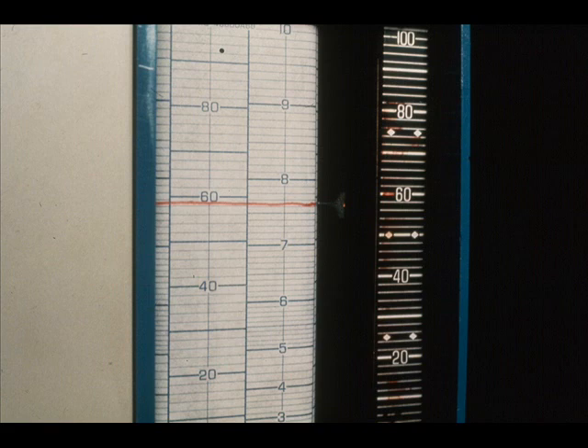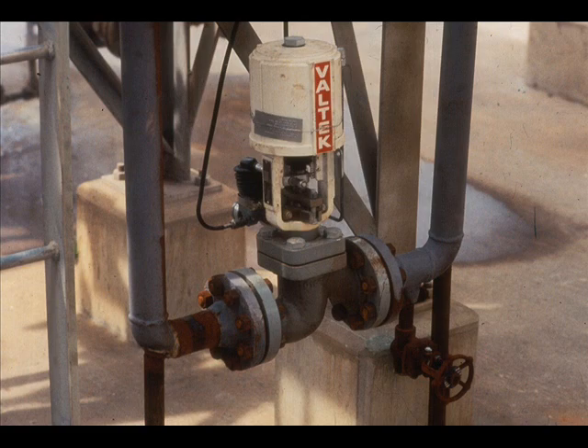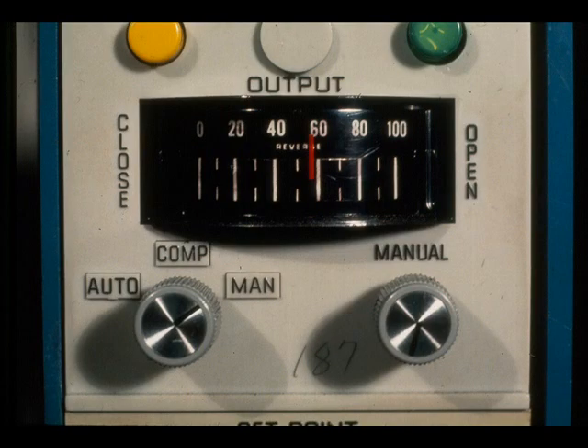Line out the record. This means the process curve should be as near a straight line as possible. Make a small step change to the process by moving the manual adjustment slightly. This will reposition the control valve slightly. The response the process makes to the open loop step change is called the reaction curve of the process. Remember, the controller is on manual. The process pen should move to a new position and line out.